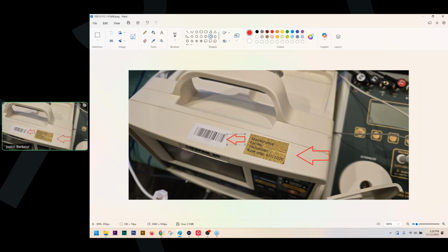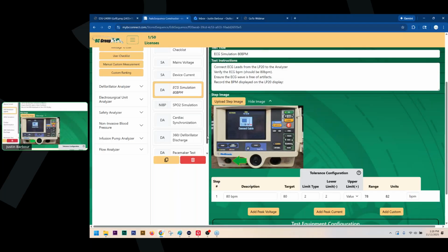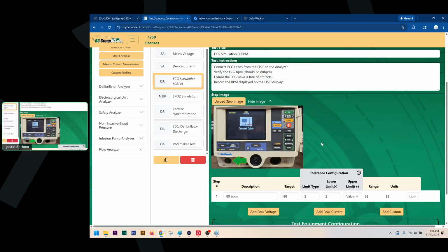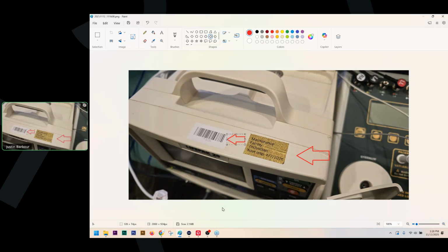So right here's the PM tag. I want my technicians to place this PM tag right here, and I will attach that right here in my walk away checklist. When I say affix PM tag to the medical device, I'll include that specific photo. That's where I want you to put the tag, right there. That's the level of documentation that I would love for you guys to start applying to your PM program.